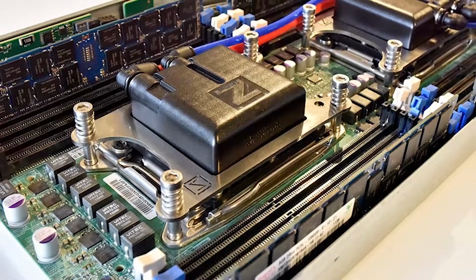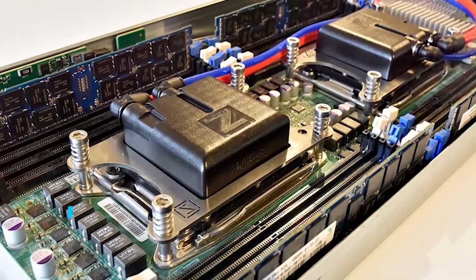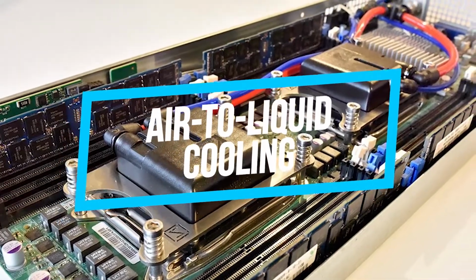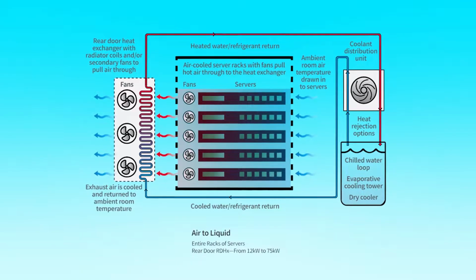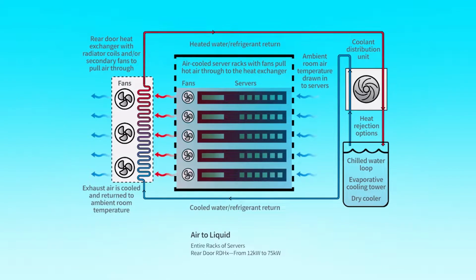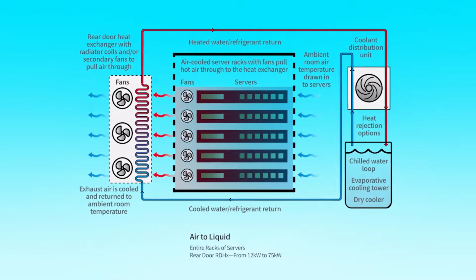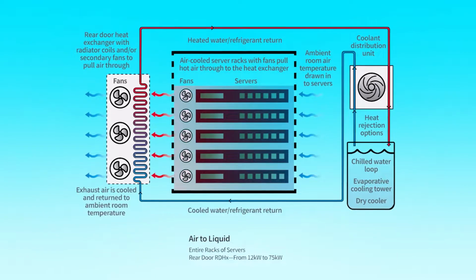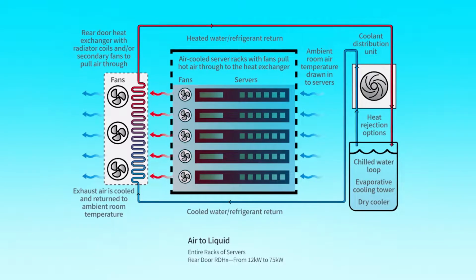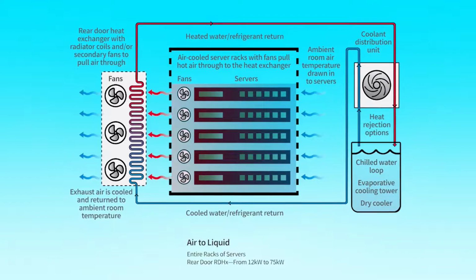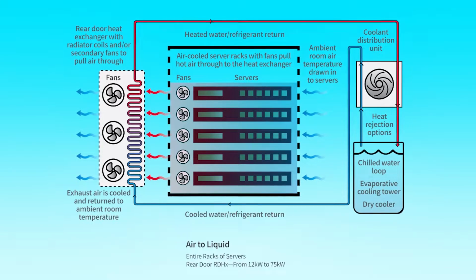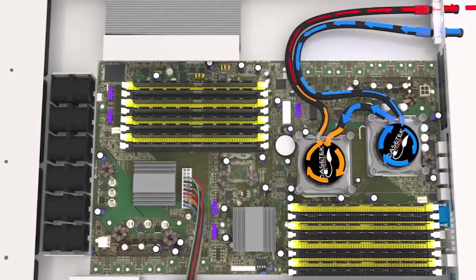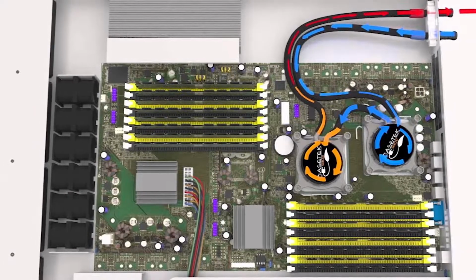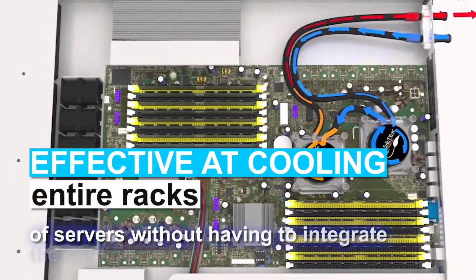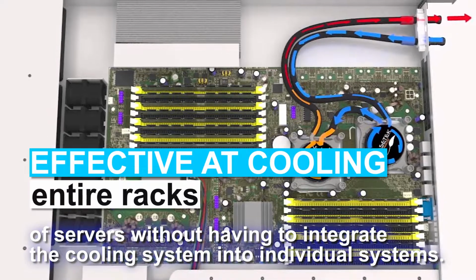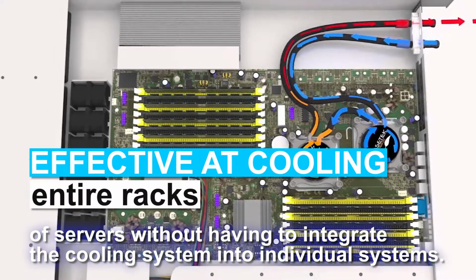The second of Supermicro's three cooling options is air-to-liquid cooling. This rack-integrated solution relies on liquid to cool the air exhausted from the systems, using a heat exchanger. Several powerful fans in the rack rear door draw hot air away from the servers and cool the air before it's returned to the data center. The cooling liquid is chilled externally to the door. This solution is effective at cooling entire racks of servers without integrating the cooling system into individual units.